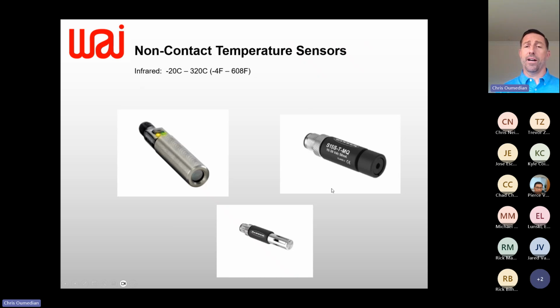We've got a few different offerings. These are all from Banner. Turck has one as well. The main basis of the technology, so we talked about RTDs, we talked about thermocouples. Main basis of the technology for non-contact is usually infrared technology. So you'll see these two on the top. These are infrared sensors. This is a low-cost way to have an amplified signal output without touching the media, and now you can measure that temperature.